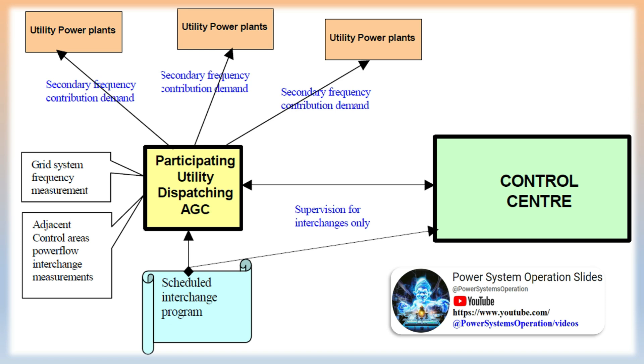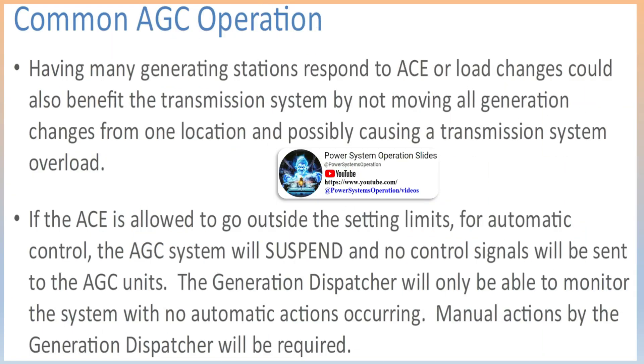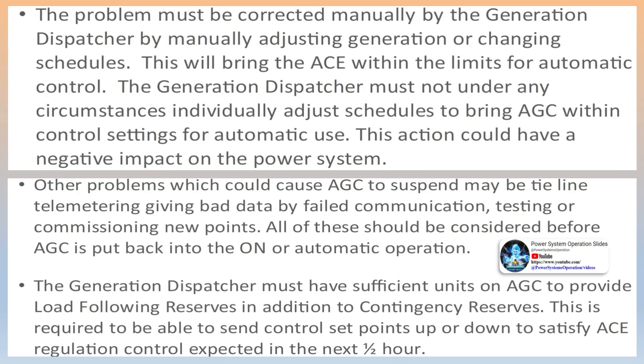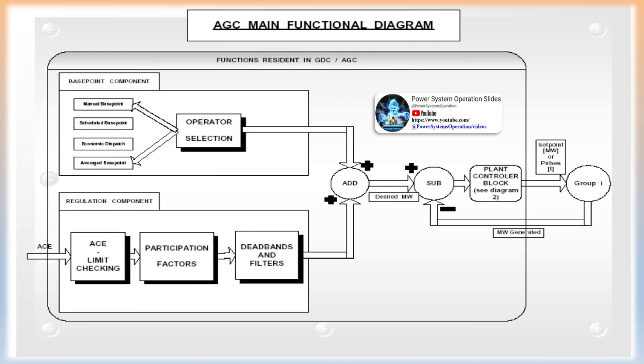ACE control parameters: ACE is a calculation performed by the AGC computer system that indicates the balance between generation and load in the control area. ACE is calculated using inputs from the power system and computer system. Tie-line bias TLB: the most commonly used ACE calculation parameter mode is called tie-line bias. This is the AGC mode that should be operating in most circumstances. In TLB mode, the ACE is calculated using the system frequency and tie-line loading. Constant net interchange CNIC: another AGC mode available to the generation dispatcher is constant net interchange. In this mode, the frequency component of the ACE calculation is removed. The AGC will control to the tie-line schedules and pulse the generation to ensure these flows are maintained. This could have a negative effect on system frequency as the AGC does not factor in the frequency and adjust for it as in TLB mode.